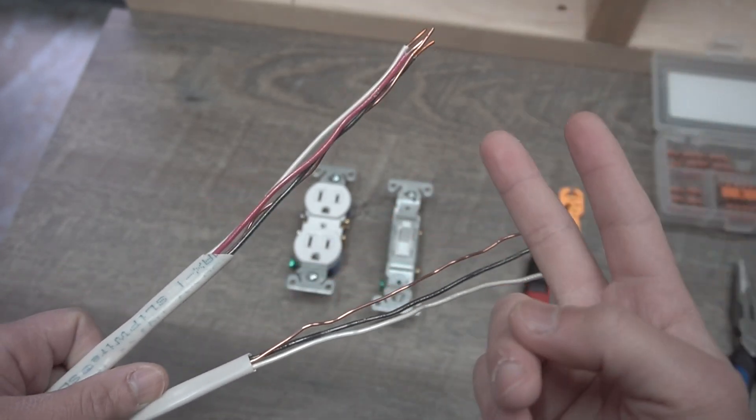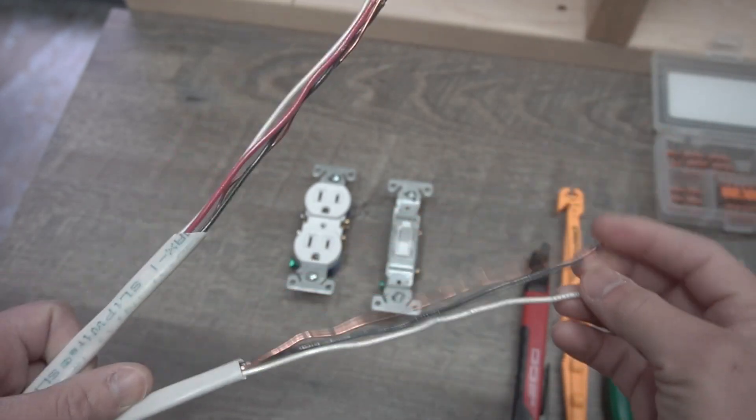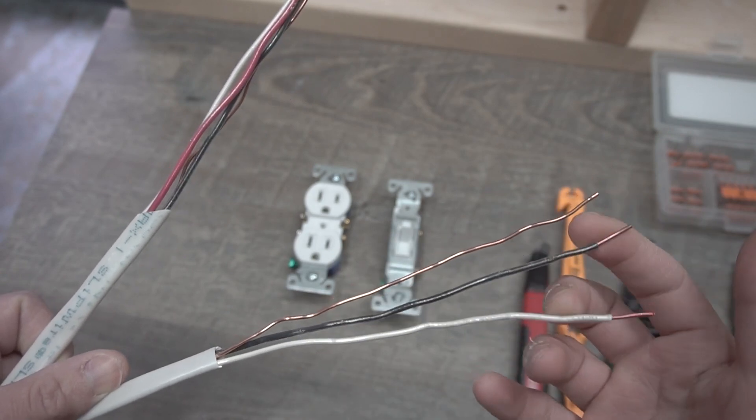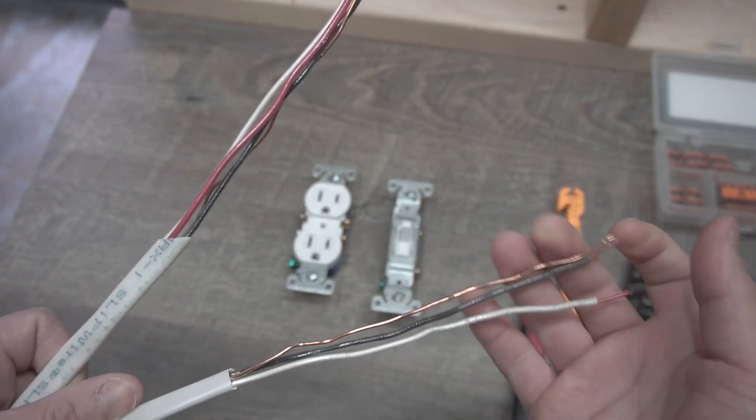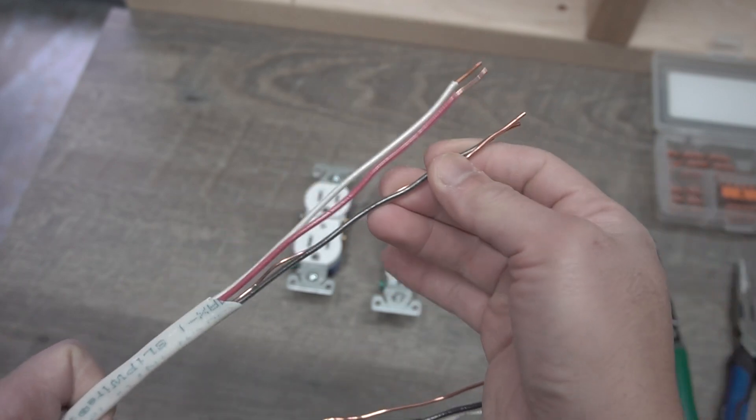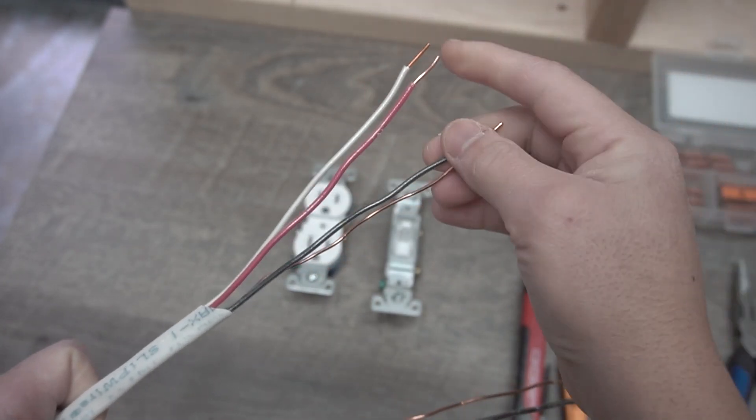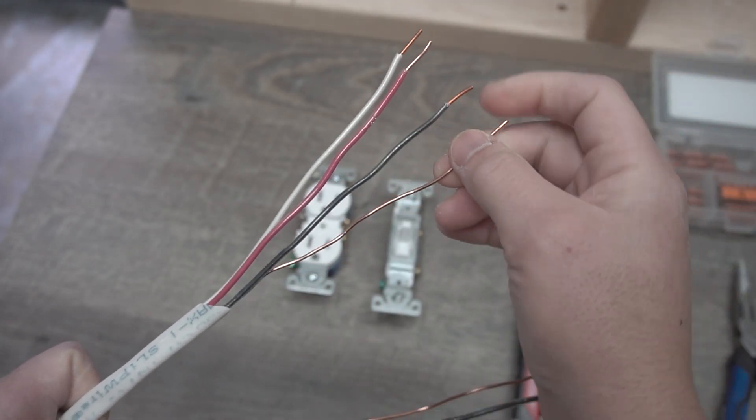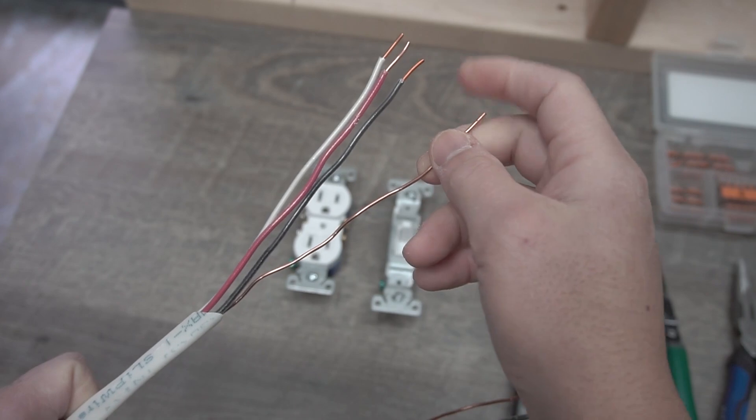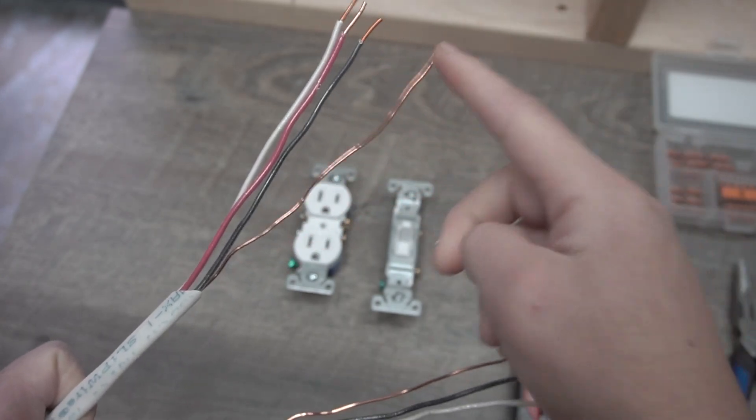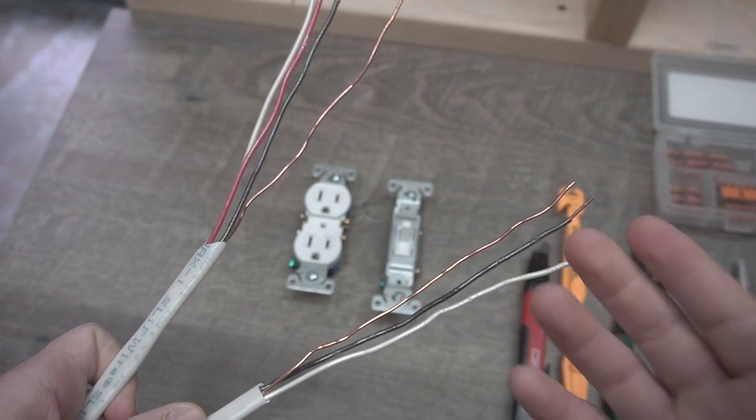We're going to be using two types of wires. We're going to be using a 14-2, which is two conductors, which is the neutral and the hot and one ground, and a 14-3, which is three conductors, which is a neutral, a red which can act as hot, and then you have a hot black right here and a ground wire. If you're using a 12 gauge wire, similar types like this one.